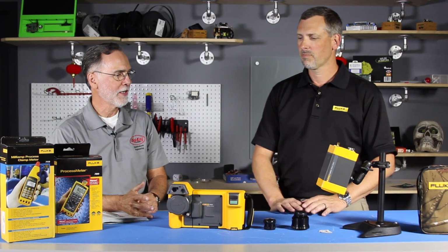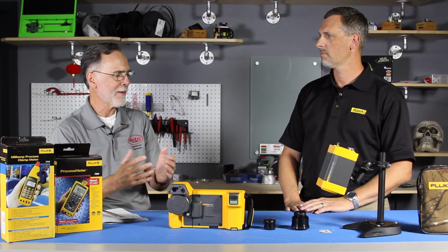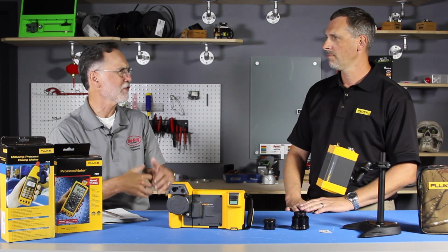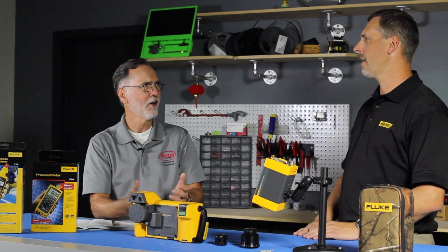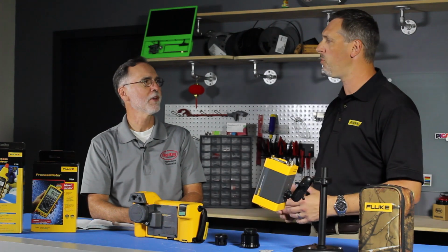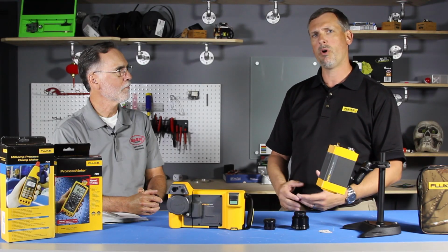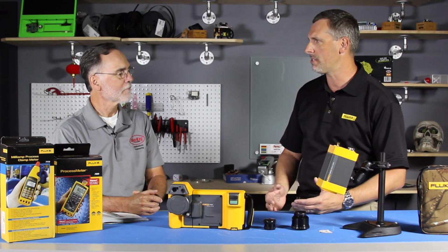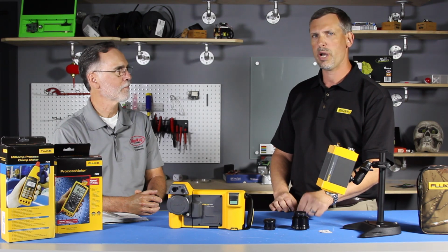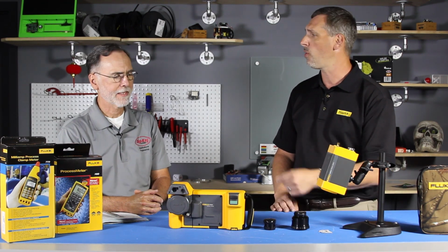So you had mentioned thermography and traces and printed circuit boards, and I'm always used to taking a thermocouple and plugging it into a Fluke meter, but this is more than that, right? That's correct. People traditionally would take a thermocouple, an RTD, a thermistor, something like that, which is a contact temperature measurement device. Now, when you're dealing with incredibly small components such as surface mount technology, when you put the bead of that thermocouple onto that device, you actually create a heat sink on that device. Therefore, you're getting inaccuracies in measurement, or can.